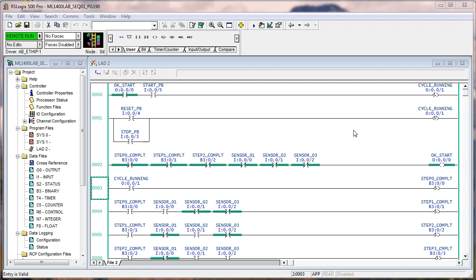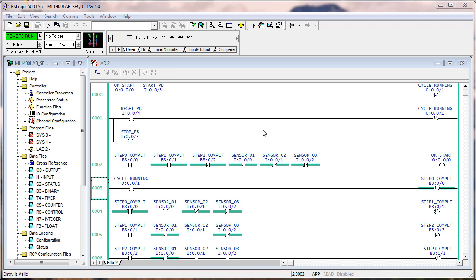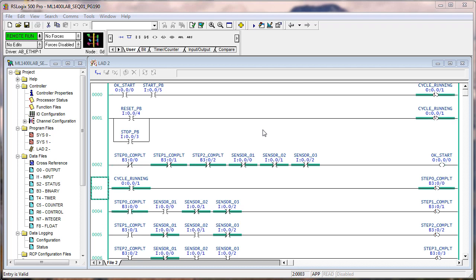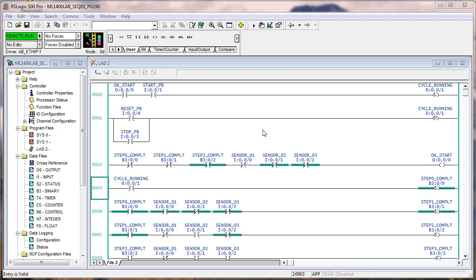So if I hit the start push button, see, you see the exact same thing down here that you saw before, step zero complete. Now if I hit the stop push button, that drops it out. And the reset button will clear it. So there's a difference between stopping it and resetting it. Let's do that again. Start it. Let's say we complete step one, and then we push the stop push button. Okay, the steps are still complete. Everything's still there. So if we push the start push button again, see, we can't get it to go again because we don't have okay to start. So we would have to reset it, get the sensor back, and then start it again.